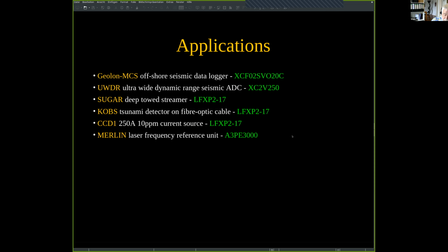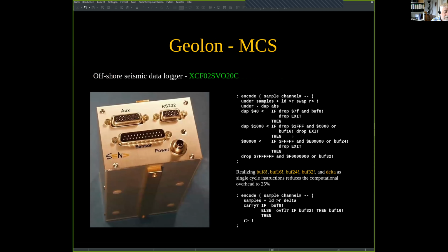Okay. Geolon MCS. So this has been a workhorse for the offshore geophysicists to record not only the XYZ geophone signals or seismometer signals, but also a hydrophone component. So this is different from the land seismic people. The offshore people always need 4 channels, and the land seismic people just can do with 3 channels. So the picture you see how it looks from outside.